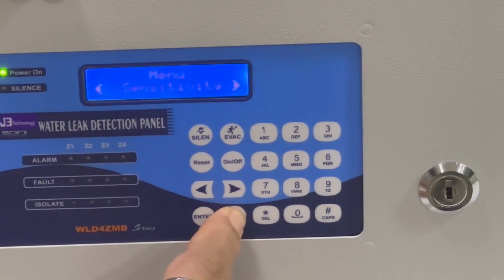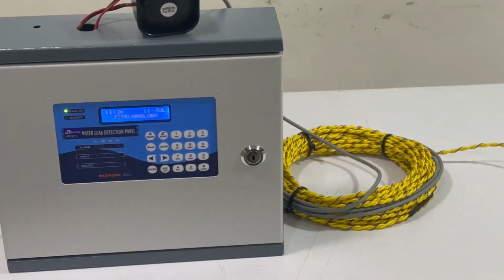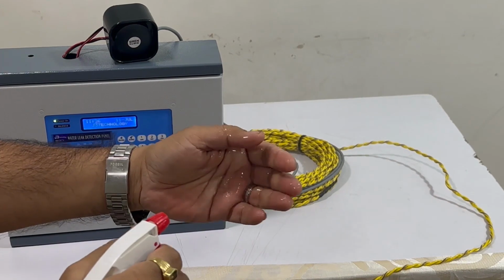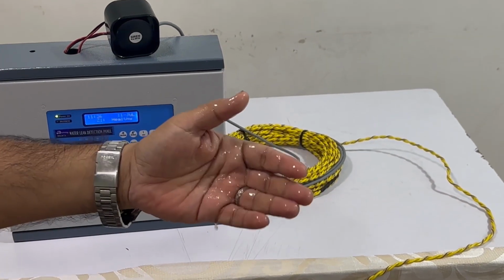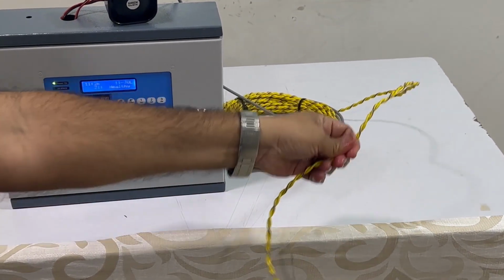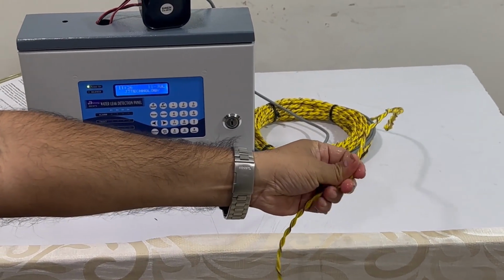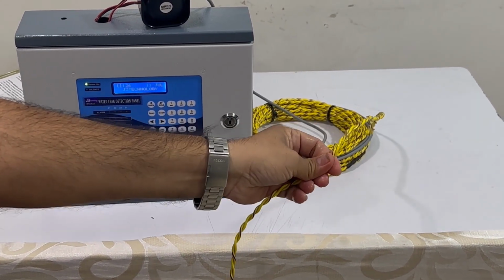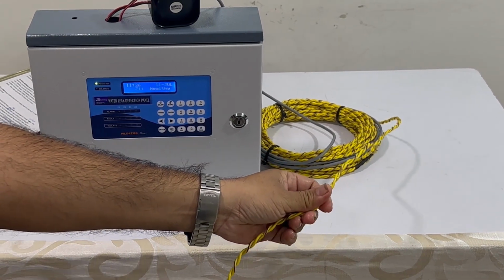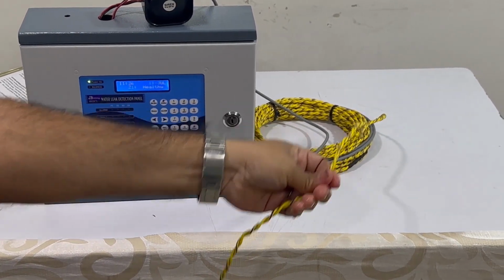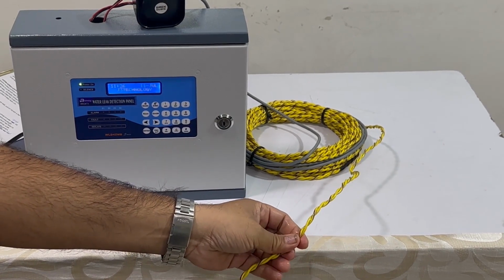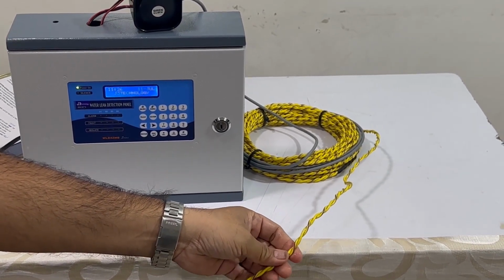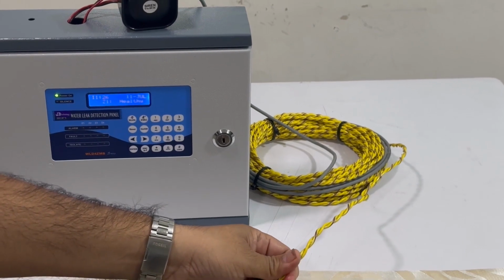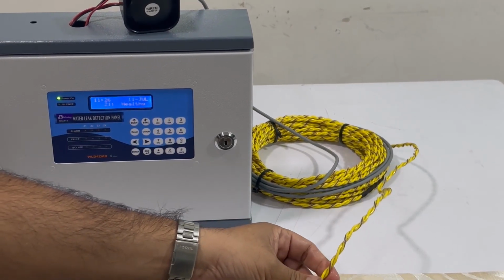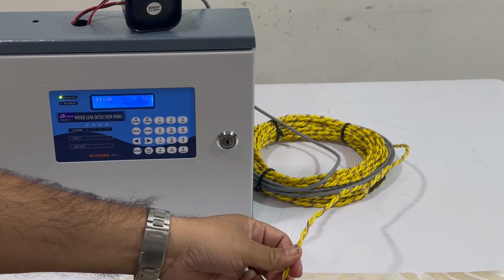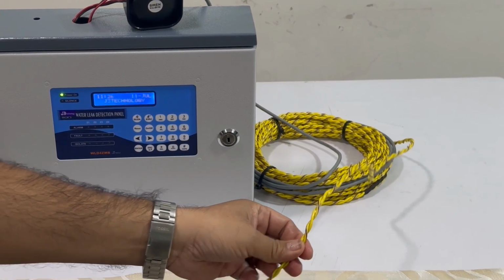Okay. Now I am testing it again with the same process. I have wet my hand and touch the cable. See, there is no alarm. There is no alarm. If I keep it on the high sensitivity and touch the cable with my wet hand, it generates an alarm. This is one of the very good features in India. We have it only in our panel. No other panel has such a feature. You can adjust the sensitivity according to your room temperature, the environment, and your surrounding area.